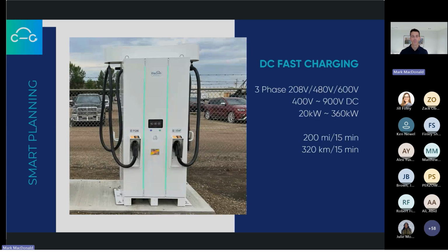The last charger you may hear referenced used to be called level 3. The way I remember it: level 1 is 120 volts, level 2 is 208 or 240, always single phase. Level 3 was always 3 phase, 208, 480, or 600. We now call level 3 DC fast charging. This is actually a charger because we're converting the AC to DC in the unit.